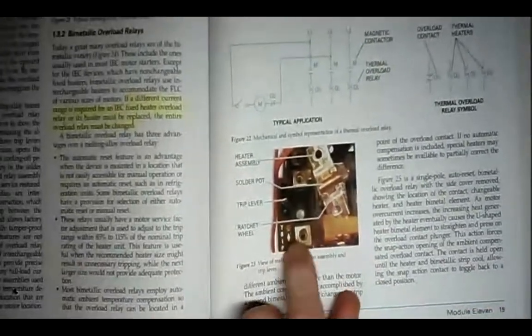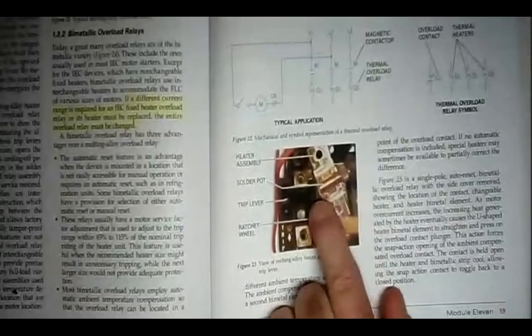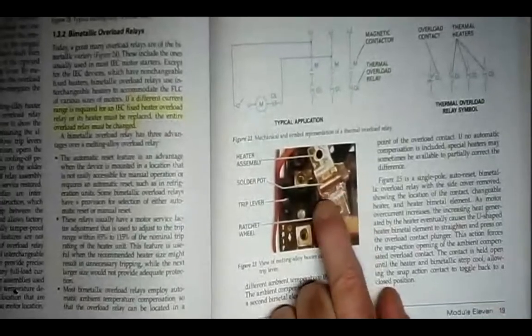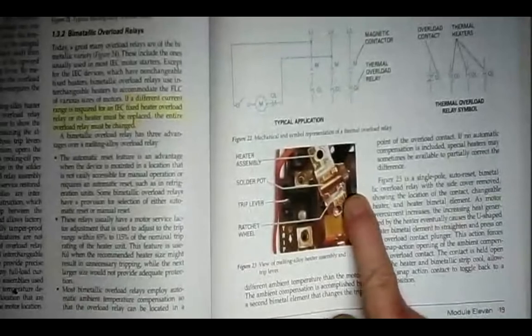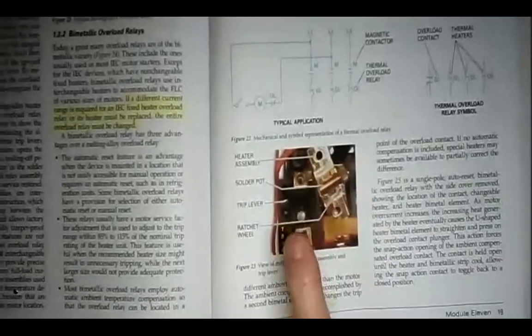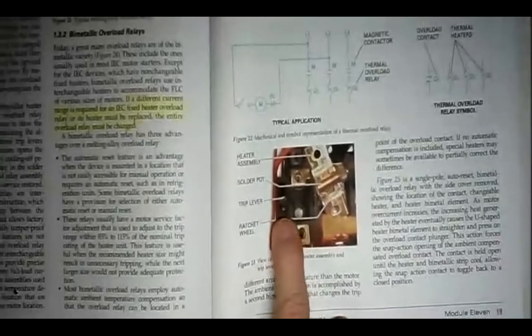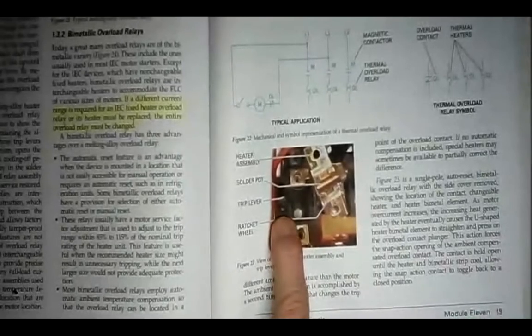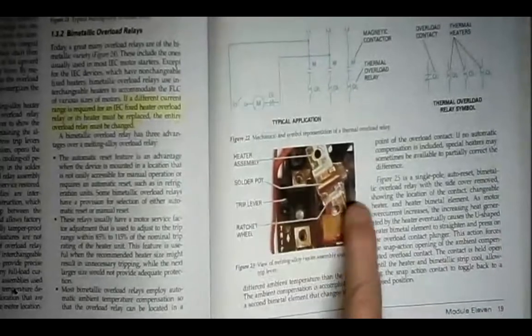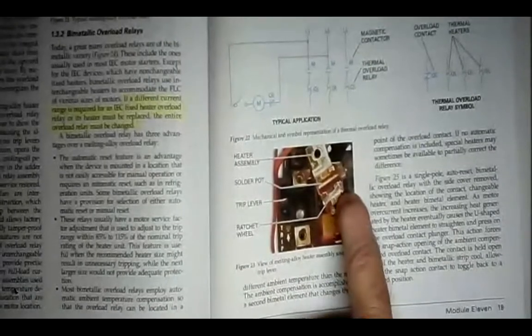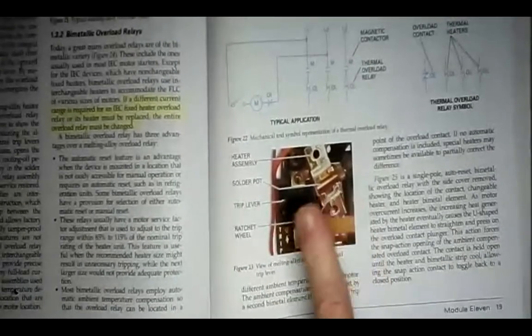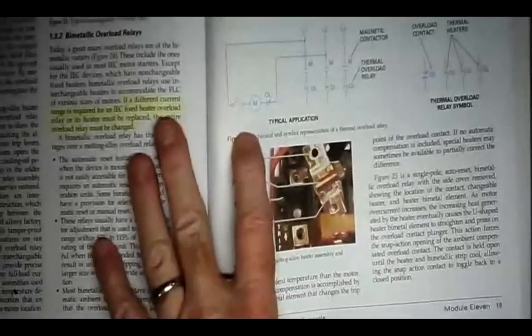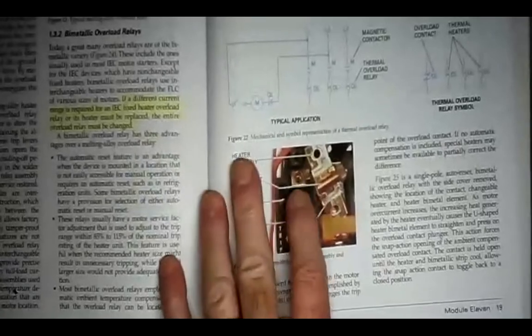Down at the bottom of page 19, it has a picture of the heater. There's the tube that has the solder in it, and there's your ratcheting wheel. And it goes across this gap, and you screw it in. There's the trip lever that is held in place by the ratcheting wheel when the ratcheting wheel will not turn. When it gets hot enough, the solder melts, the wheel turns, the spring opens the contacts, and the motor stops. That's how we're getting overload protection for that motor.